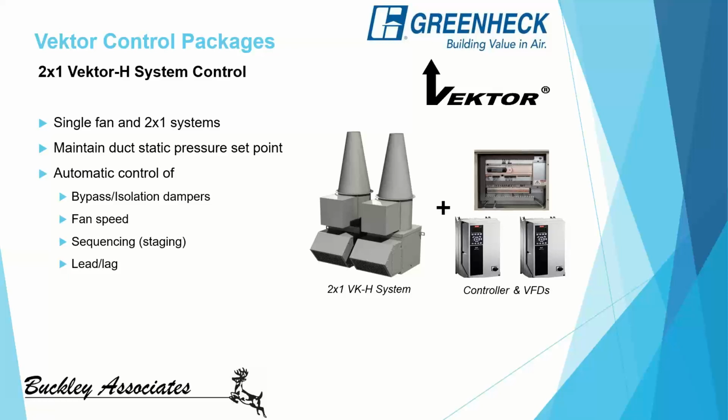So on control packages, Greenheck has started packaging controls; they've started with the Vektor H system. We can do a 2x1 control system on those, and that comes with a microprocessor control. Very, very similar to what Greenheck provides on the DOAS systems. And with that system, we can maintain duct static pressure set point and control fan speed sequencing. So if you have an N+1 configuration, we can control that and do the lead-lag sequencing and the bypass and isolation dampers as well. So for smaller systems, we now have that control package. Greenheck is working on developing control packages on the larger fans as well, but this is their introduction to that market.